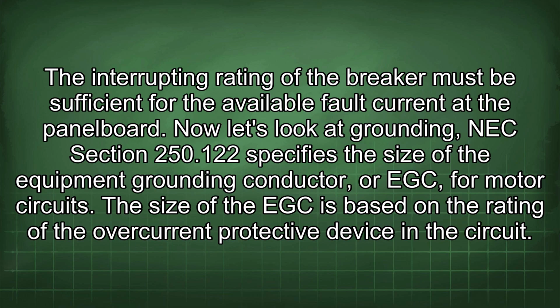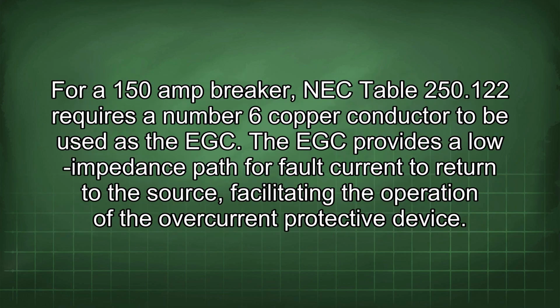Now let's look at grounding. NEC section 250.122 specifies the size of the equipment grounding conductor, or EGC, for motor circuits. The size of the EGC is based on the rating of the overcurrent protective device in the circuit. For a 150 amp breaker, NEC table 250.122 requires a number 6 copper conductor to be used as the EGC.